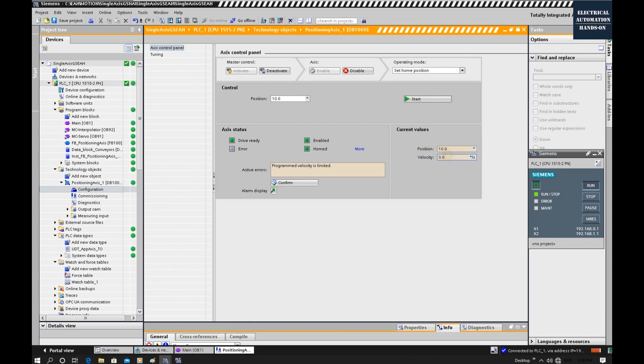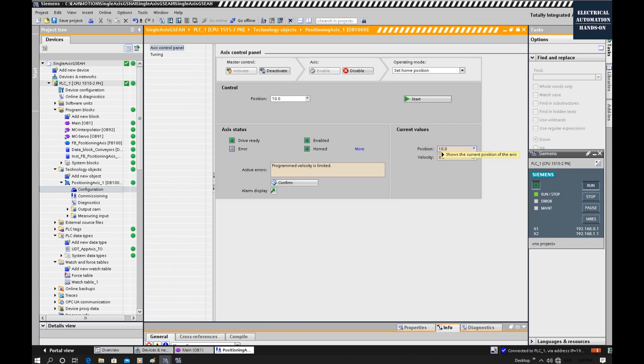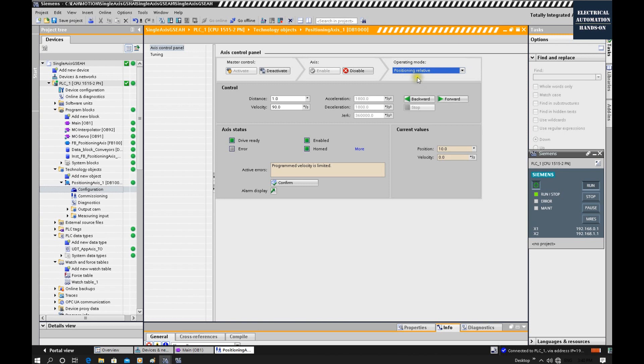It will set 10 degrees directly to this axis. After this home position, basically our encoder, whatever we are using the absolute or the incremental encoder, our axis will know logically this current position is 10. After this, we can start to verify if our positioning can control properly. Basically, we need to verify our gear ratio setting or the gear mechanical relationship.